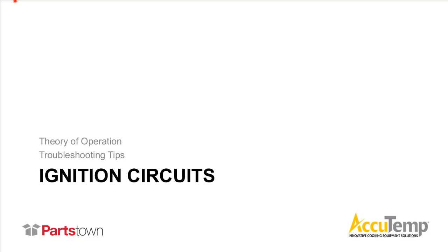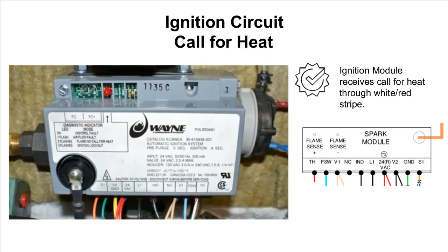Well, if we know those circuits are good, the first thing that we're going to look for is the LED light on the module, which is right here. If you know both sides of your circuit are good and you have a solid red LED on the module, that is showing a control fault within the module itself. Our advice at that point would be to restart, as in power the unit off and back on. Does the control fault resume? If it does, you have a defective module.